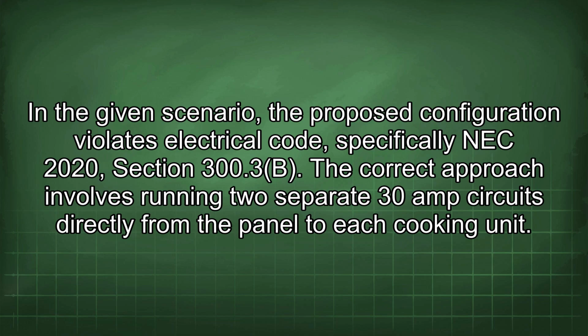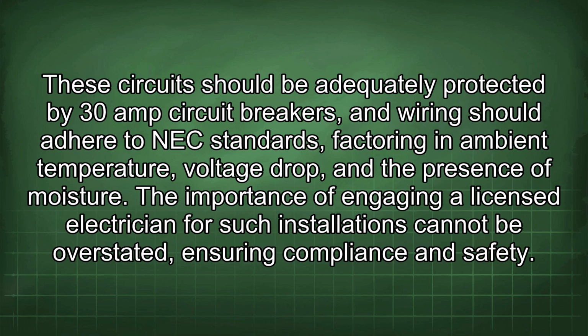In the given scenario, the proposed configuration violates electrical code, specifically NEC 2020 Section 300.3(B). The correct approach involves running two separate 30-amp circuits directly from the panel to each cooking unit. These circuits should be adequately protected by 30-amp circuit breakers, and wiring should adhere to NEC standards, factoring in ambient temperature, voltage drop, and the presence of moisture. The importance of engaging a licensed electrician for such installations cannot be overstated, ensuring compliance and safety.